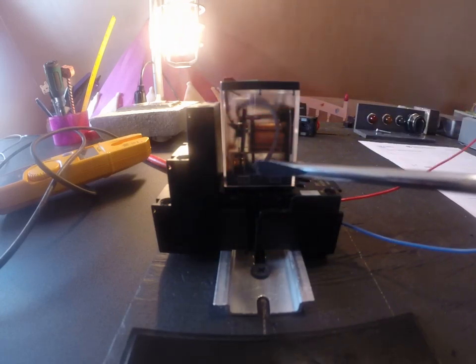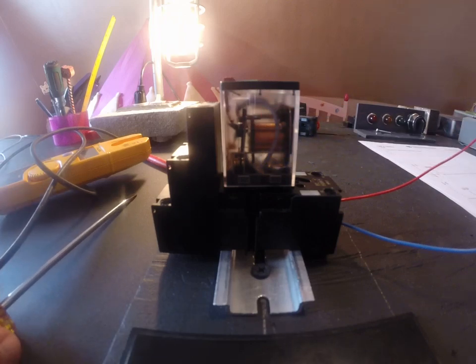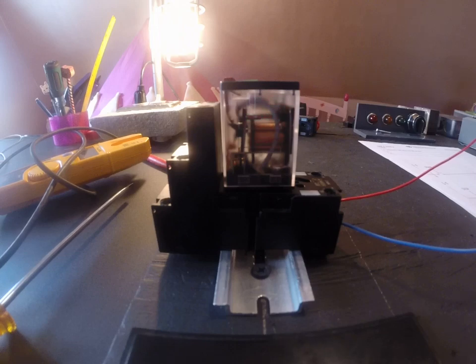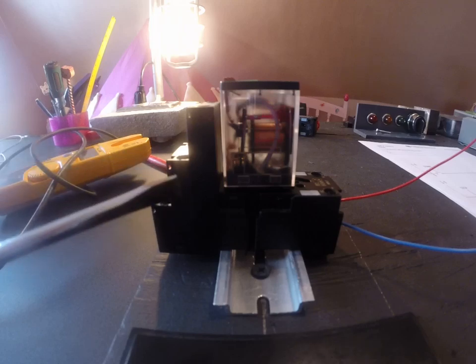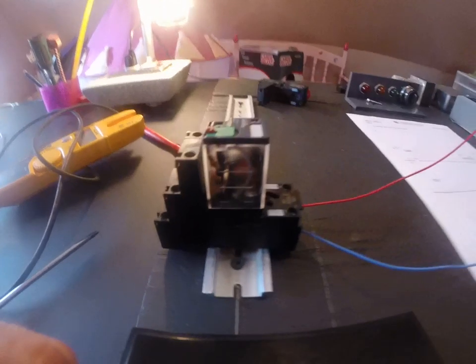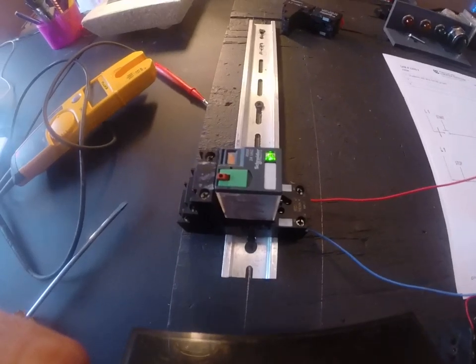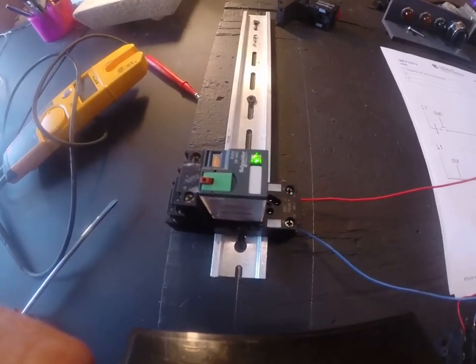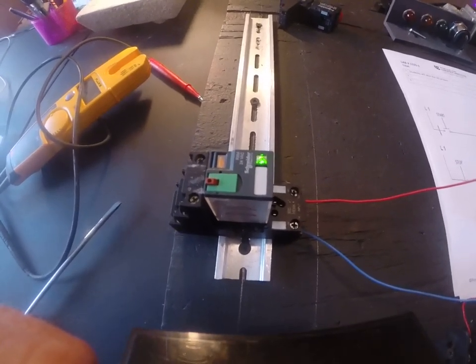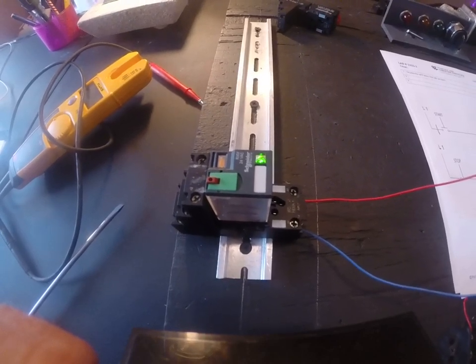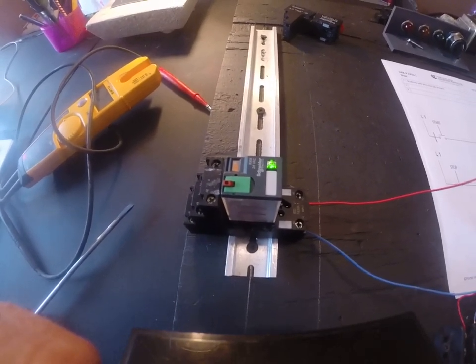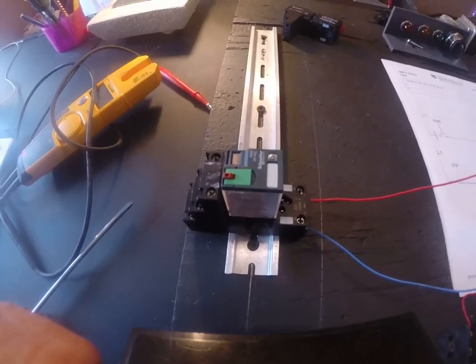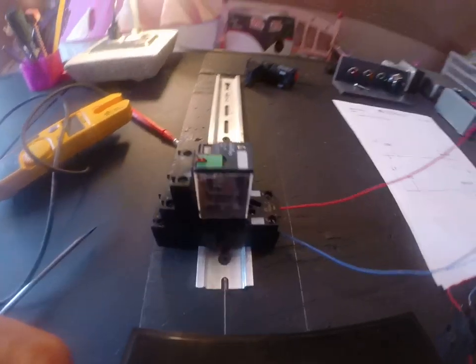So how that works is if I press the start button, which is the lab that we did yesterday except we're now energizing a coil instead of a light. If I press this start button and hold it you'll see two things happen. One you'll see an indicator light come on this coil, this relay, saying the coil is energized. And I have to keep my finger on it for now because I have not built a holding circuit yet. If I release it the coil is de-energized.